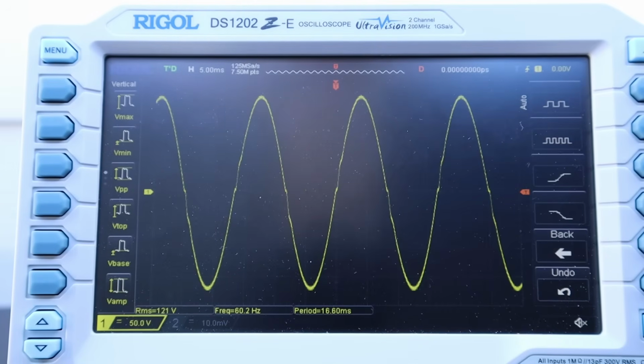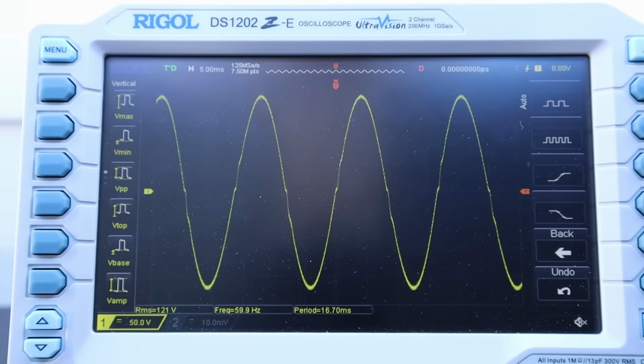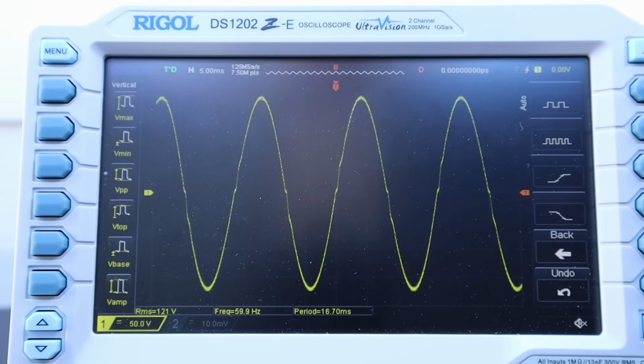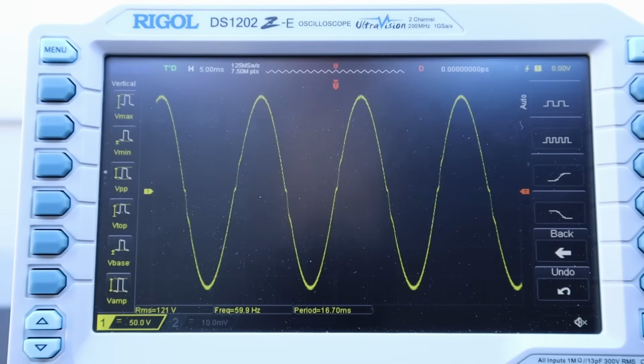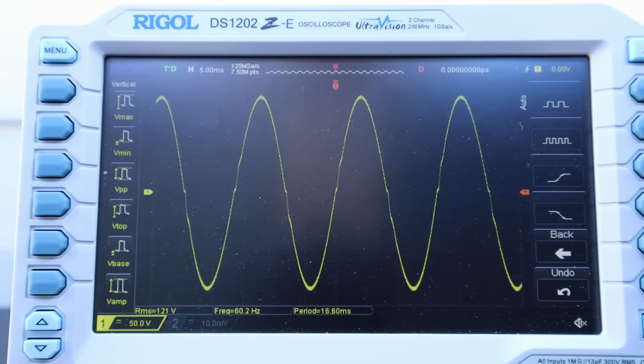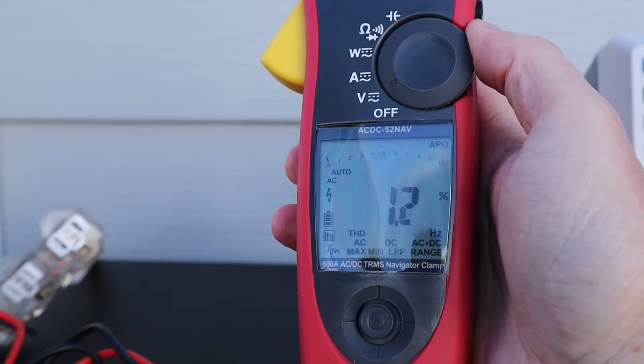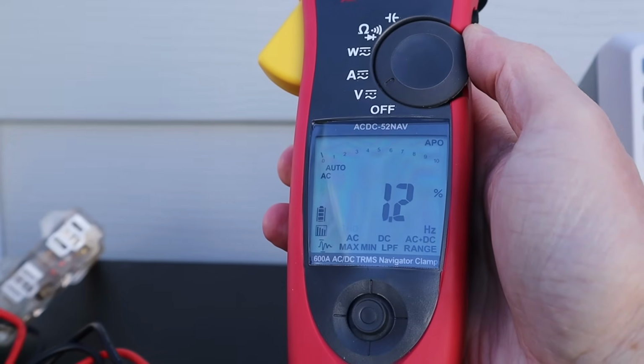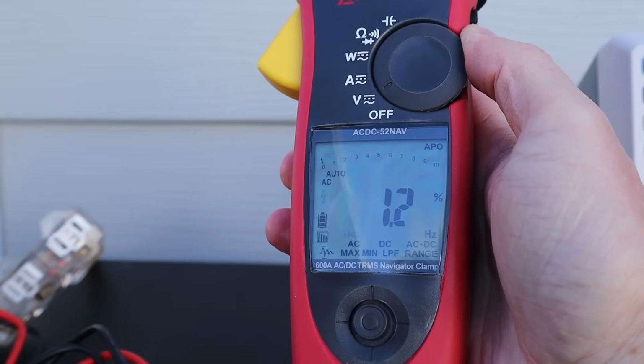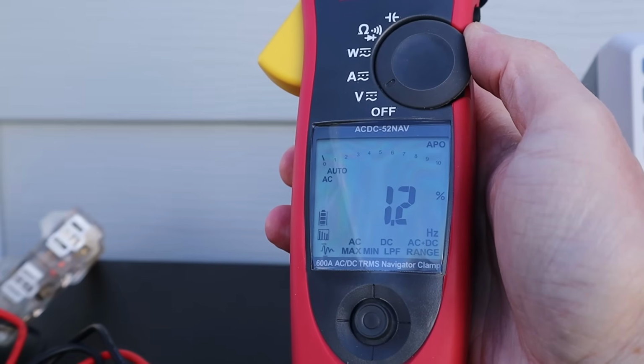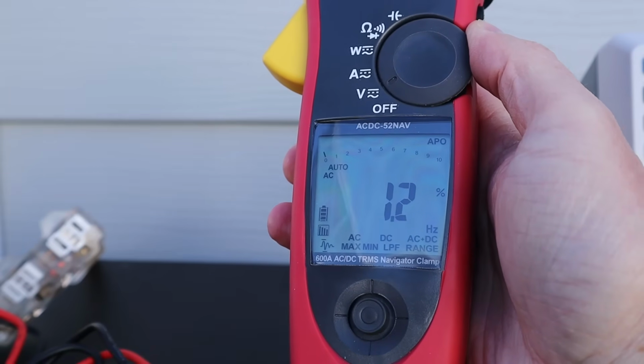So my oscilloscope is connected to the inverter output. We are showing a pure sine wave output. It's at 121 volts and 60 hertz. You can see it's between 59.9 and 60.2 hertz. And this is what you'd expect from a modern power station. You get a very clean sine wave output. Measuring the total harmonic distortion on the power station, we are seeing 1.2%, so just a little bit higher than the inverter generator, but well within tolerances. You just want it under 3%.